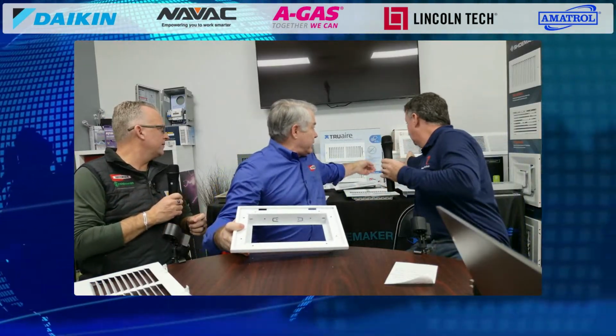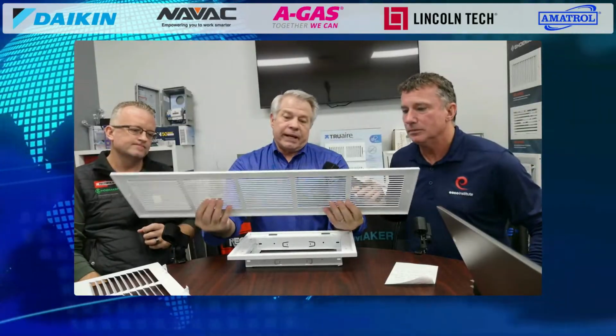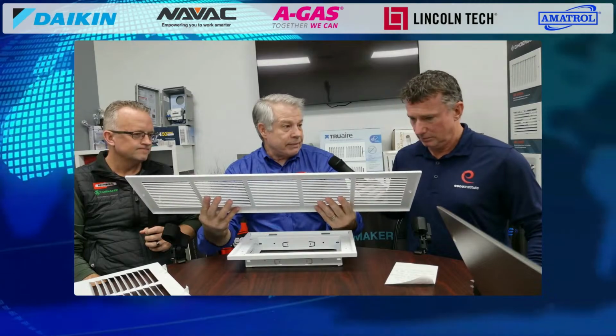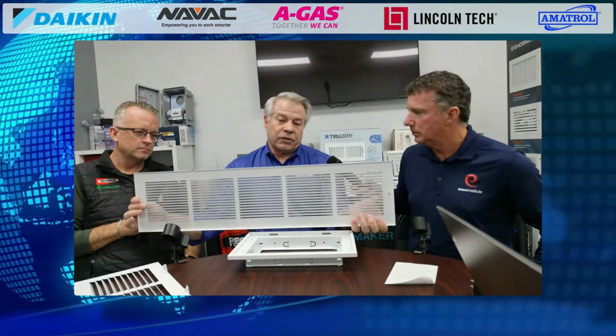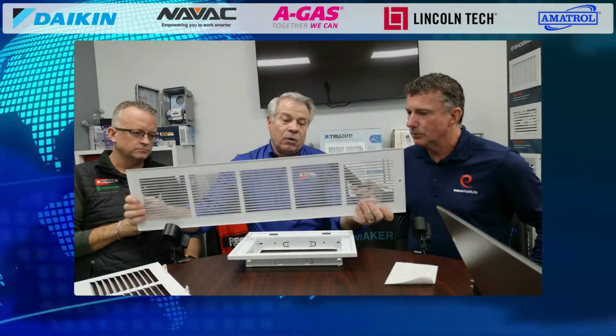So when it's just a grill, and I don't have one here. There's that. Yep, that's one. That's a long flat one there. But we got this. This is just a return grill, right? On this, they say it should be designed for 500 feet per minute across the neck. Not so much the face, but the neck, the duct. And as you can see, it's just a flat grill. This one mounts flush against the surface, whether it's a ceiling or a wall.